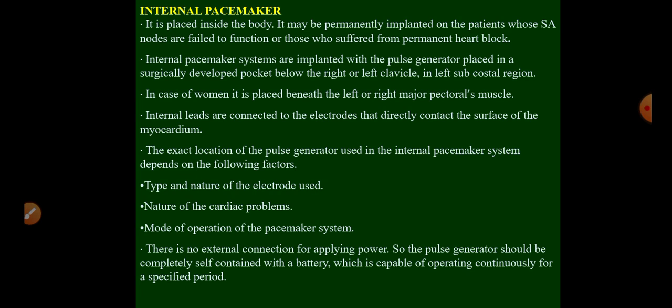Internal leads are connected to the electrodes that directly contact the surface of the myocardium. The exact location of the pulse generator used in the internal pacemaker depends upon the type and nature of the electrode used, the nature of the cardiac problem, and the mode of operation of the pacemaker system. There is no external connection for applying power supply, so the pulse generator should be completely self-contained with a battery which is capable of operating continuously for a specified time period.